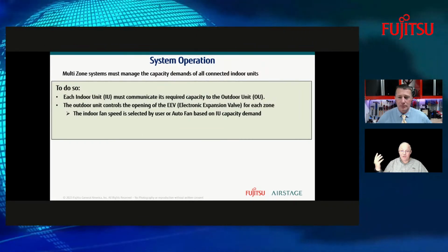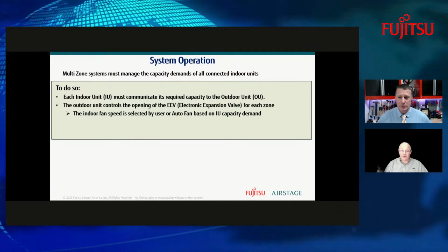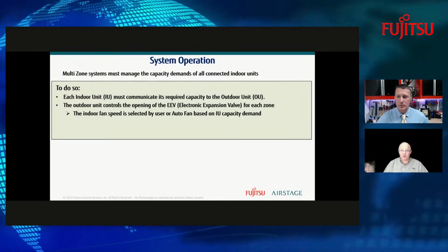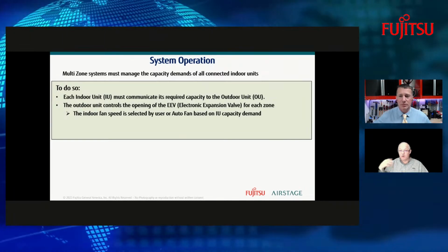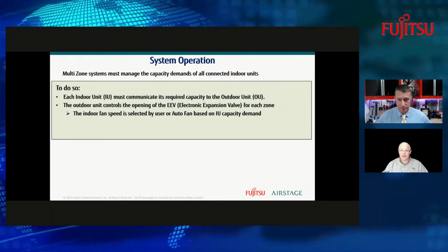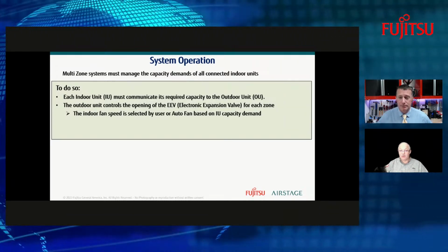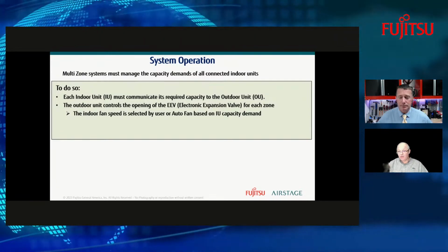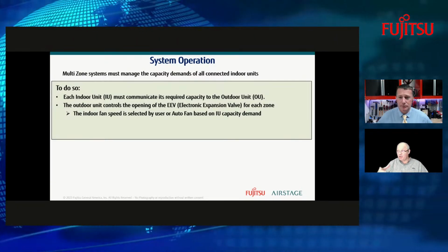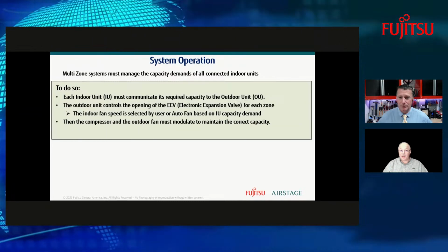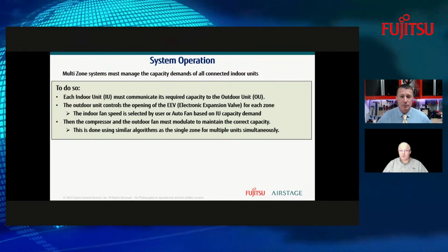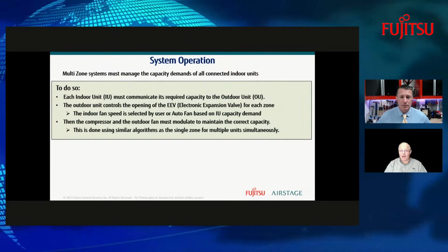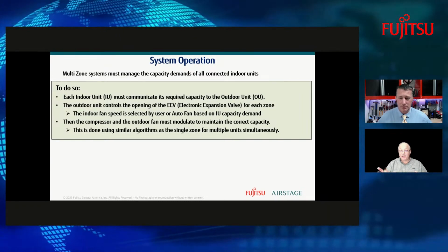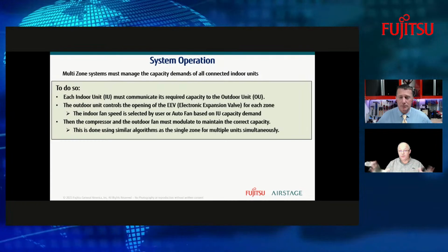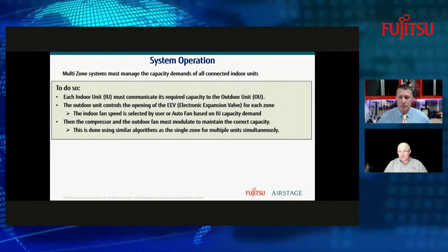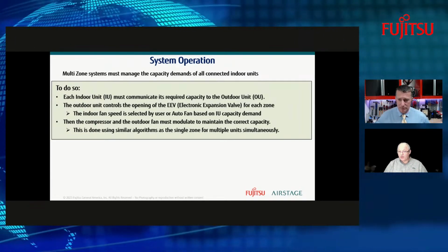But in a standard system, you're only going to get so much air out of a vent. Well, that's not enough. That's the beauty of a multi-zone on this house: this office could have its own indoor head working with that multi-zone, and I could get the amount of cooling I need depending upon how much heat I'm generating in this room at the time. Absolutely. So this compressor and the outdoor fan motor have to be able to modulate to maintain the correct capacity. Depending upon what's going on with the different zones is going to depend upon what speed the compressor is going to have to run at.